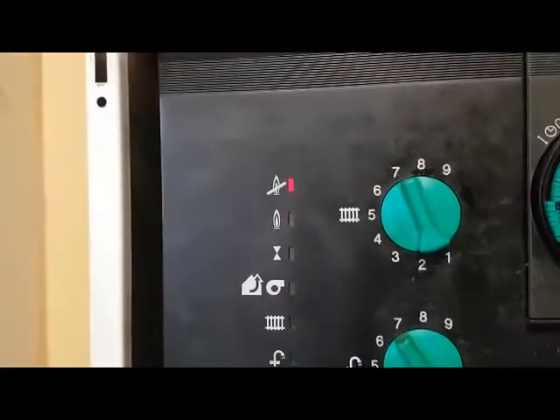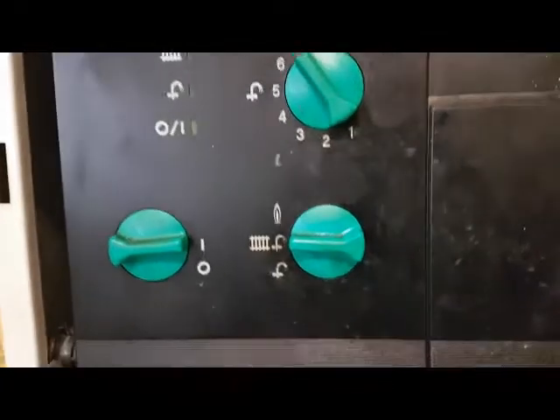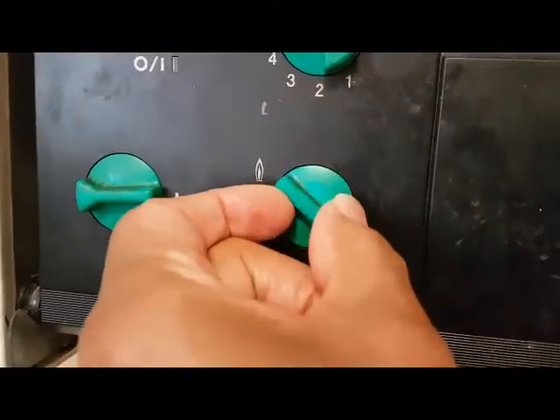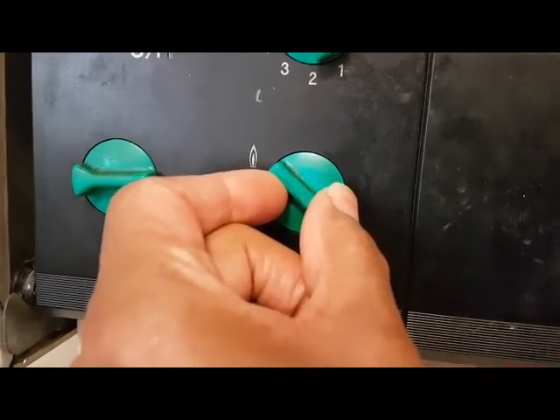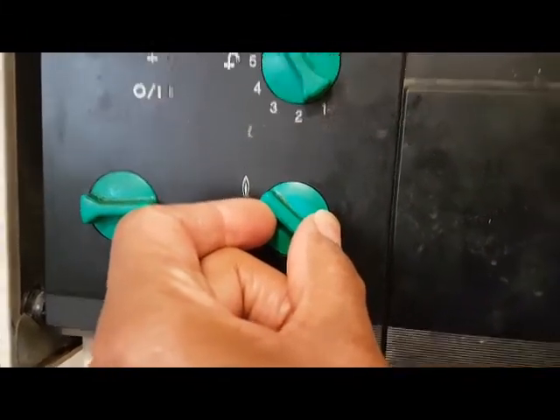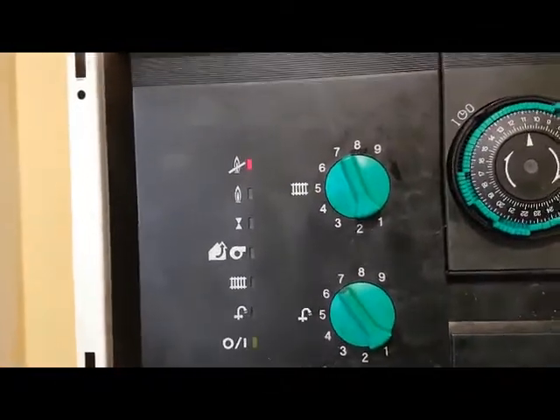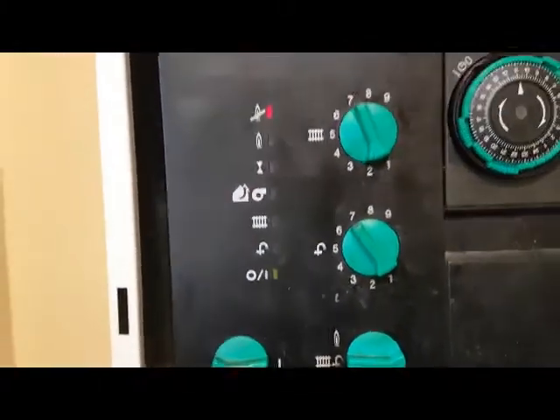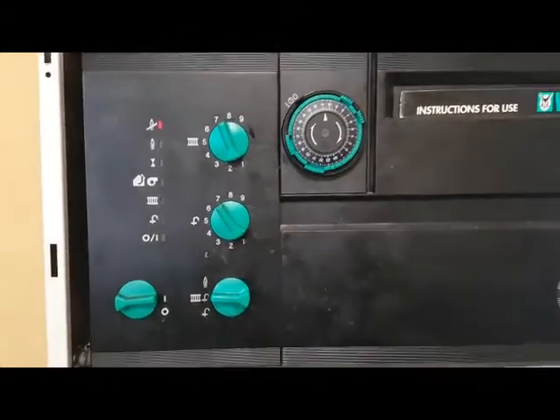As you can see, the lockout light is on. The problem is it won't reset, so I'm going to try and reset it by holding this knob, pushing it up, holding it for 10 seconds, and then releasing. As you can see, it's still on — it's not resetting. So if you've got this problem, you've got a PCB fault.